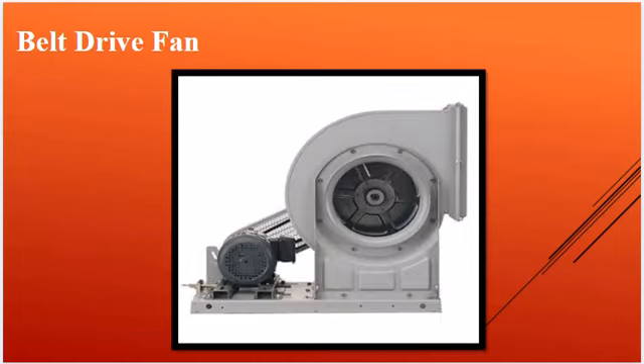Belt drive fan. Belt drive fans offer greater flexibility because the belt allows for speed adjustments that can be tailored to specific needs. However, these fans are susceptible to belt wear, which can lead to slippage and energy loss. Routine checks on belt tension and alignment are necessary to maintain efficiency and prevent breakdowns. While they require more maintenance than direct drive fans, they're valuable for systems where precise speed control is needed. Properly maintained, belt-driven fans can balance flexibility and performance.